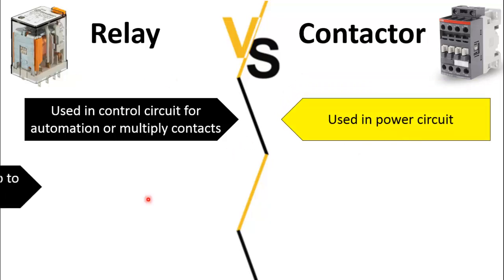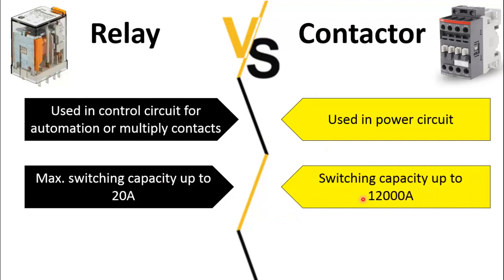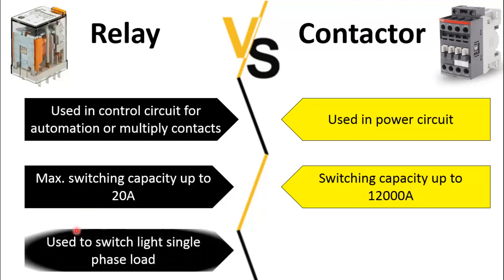Another difference is the maximum switching capacity of a relay is up to 20 ampere. This type of relay, which has a high current rating, is called the power relay, but most relays are used only to energize the coil of a contactor. Whereas for the contactor, the switching capacity is up to 12,000 ampere because it is used to switch heavy loads.